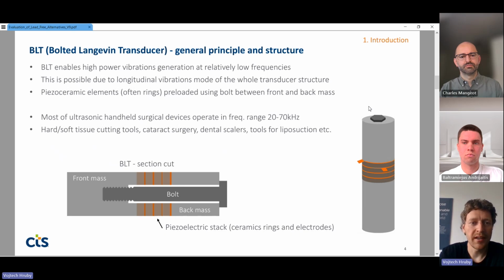A bolted Langevin transducer enables high power generation at relatively low frequencies, and this is possible due to the longitudinal vibrational mode of the whole transducer structure. A bolted Langevin transducer consists of front and back mass made from metal and a central bolt, which is used to preload a piezoceramic stack in the middle. Most ultrasonic handheld surgical devices operate in a frequency range between 20 and 70 kHz, and they are used for hard and soft tissue cutting tools, tools for cataract surgery, dental scalers, tools for liposuction, etc.